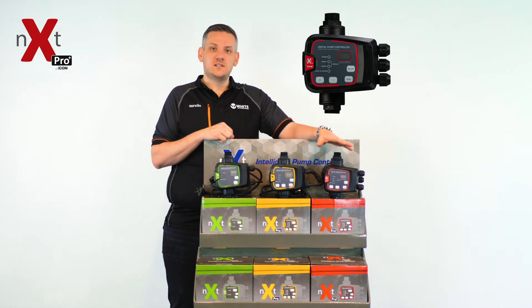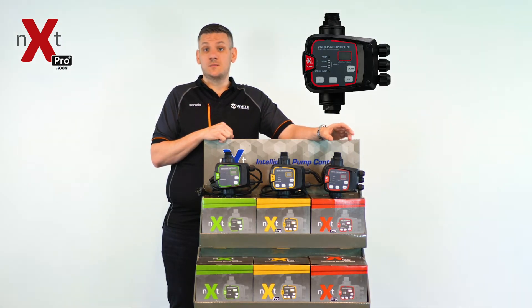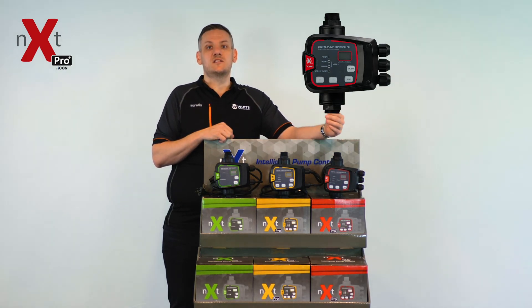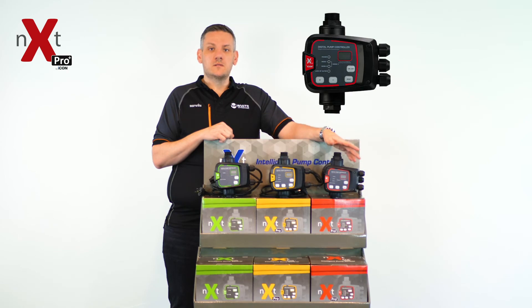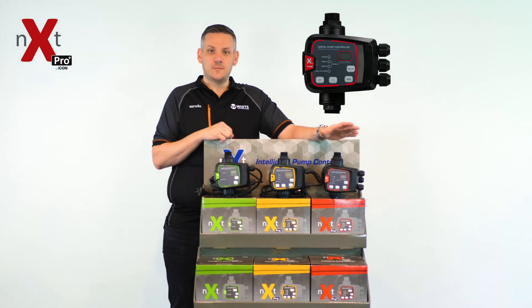It can run in what we call duty standby. It also has an added third mode of operation — duty assist — great for when you need higher pressures, allowing a second pump to turn on as the system requires to boost pressure or flow. It also alternates starts to make sure pumps wear evenly, designed for higher-level household through to light industrial applications.